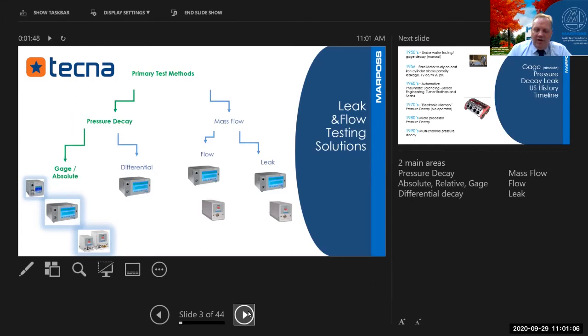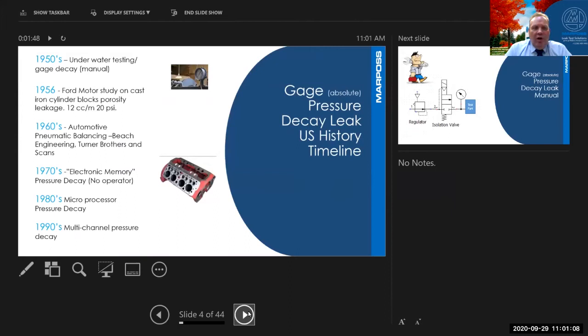Let's give you a little bit of history on pressure decay. What we're talking about is in the 1950s, primarily underwater testing and gauge decay. This was all manual testing at this point. Most of it consisted of sealing up a test part, putting it underwater, pressurizing with air and watching the bubbles come out. In 1956, there was a study done by Ford Motor.